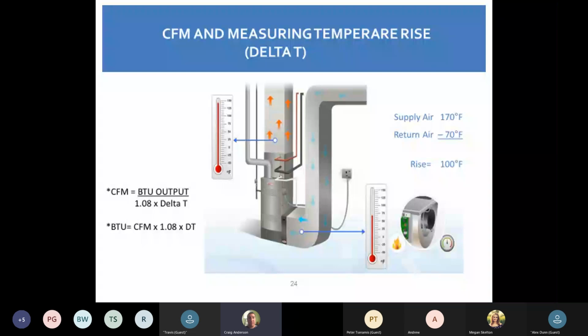We used to get a lot of calls on code 3, which is pressure switches. We're getting more calls on code 4, code 7, which is high limit errors. And they go away when we take the filter out. So we have to be very mindful of what we have in there and what this furnace is doing. So temperature rise is one of those big things that we need to check.